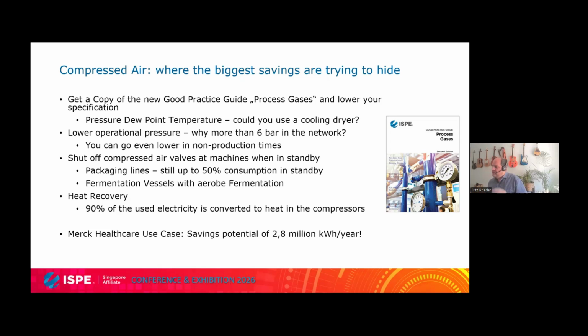But if you can't specify a +3 or higher, you could even use a cooling dryer, which is very efficient and much cheaper than an adsorption dryer, which is typically the equipment of choice.